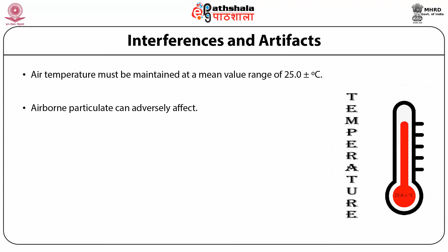The balance room's relative humidity must be maintained at a mean value of 45 plus or minus 5%. Its air temperature must be maintained at a mean value of 25 degrees centigrade, and airborne particles can adversely affect accurate mass measurement of the filter.